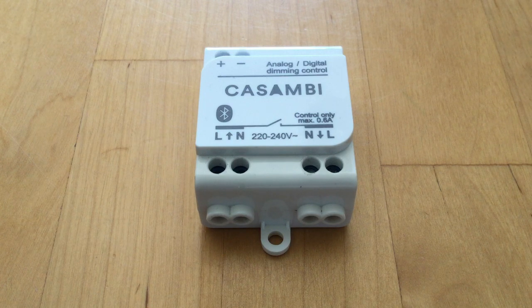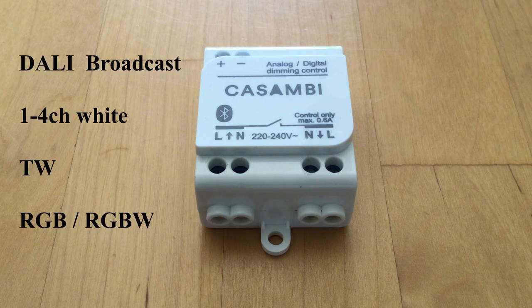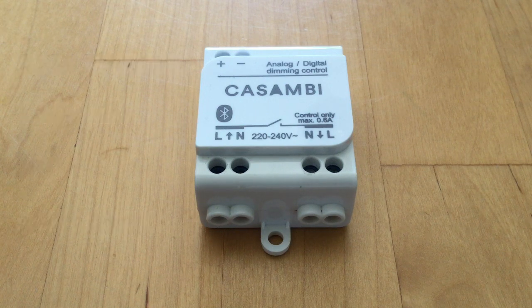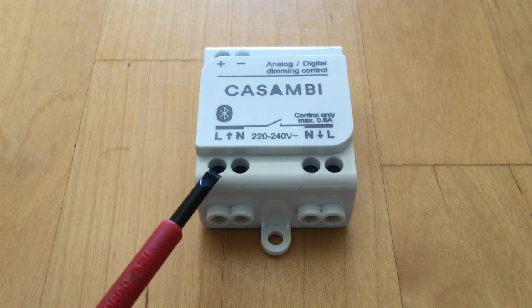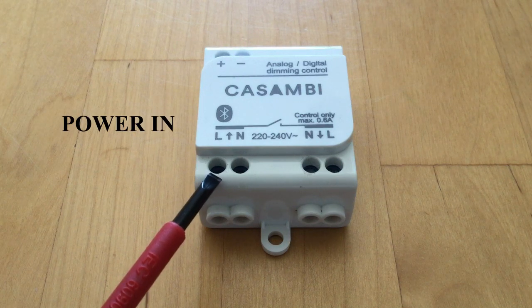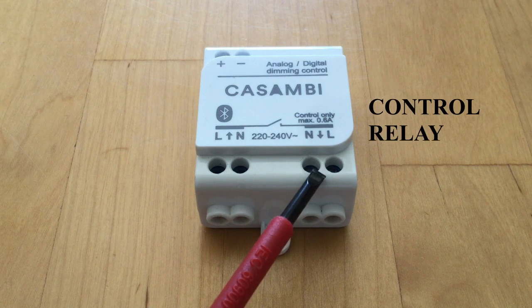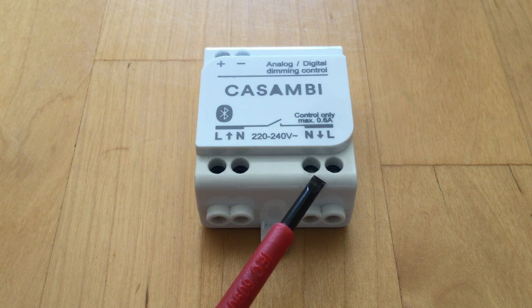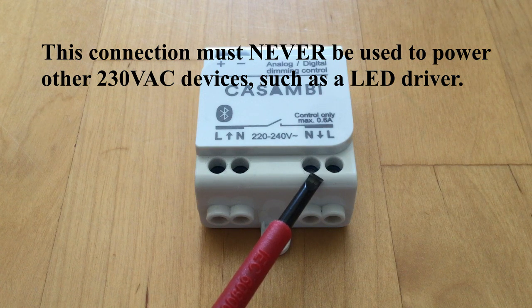Various profiles can be used for this device depending on the type of load that you want to control. So for example, DALI broadcast, multi-channel white, tunable white, or RGB. The device itself is powered from 220 to 240 volts input. The output here must only be used when connecting a relay. You must not power the LED driver from this output.